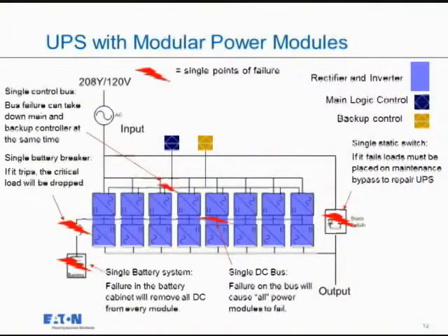Single input, single output. I've got basically the power modules. They all shared a common battery. They had a bypass, and they had an external control system. The first stage of progress by our design teams was to look at it and say, you know what, we need to start removing single points of failure. That control module is proven to be our single point of failure.